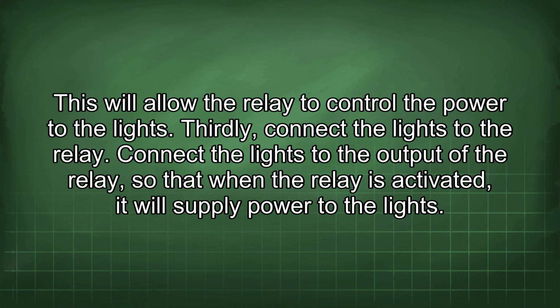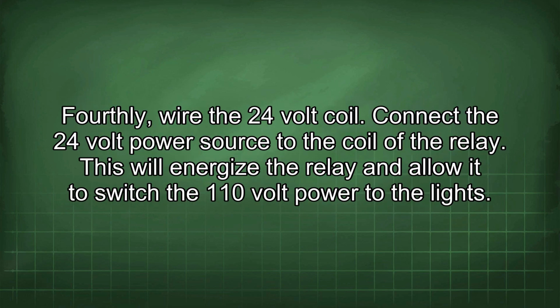Thirdly, connect the lights to the relay. Connect the lights to the output of the relay so that when the relay is activated, it will supply power to the lights. Fourthly, wire the 24-volt coil. Connect the 24-volt power source to the coil of the relay. This will energize the relay and allow it to switch the 110-volt power to the lights.